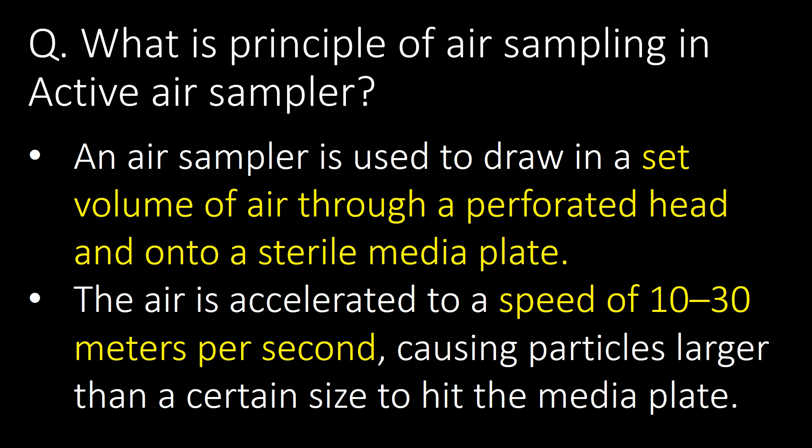Basic and important: what is the principle of air sampling in an active air sampler? An air sampler draws in a set volume of air through a perforated head and onto a sterile media plate. The air is accelerated to a speed of 10 to 30 meters per second, causing particles larger than a certain size to impact the media plate.